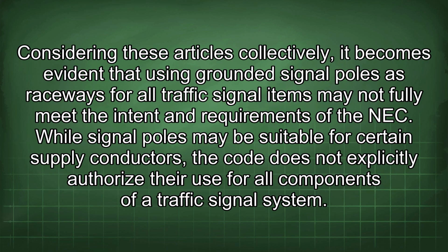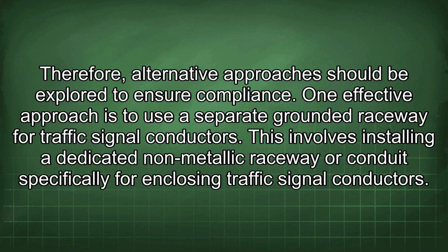Considering these articles collectively, it becomes evident that using grounded signal poles as raceways for all traffic signal items may not fully meet the intent and requirements of the NEC. While signal poles may be suitable for certain supply conductors, the code does not explicitly authorize their use for all components of a traffic signal system. Therefore, alternative approaches should be explored to ensure compliance.